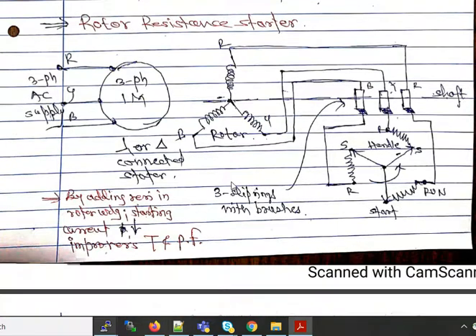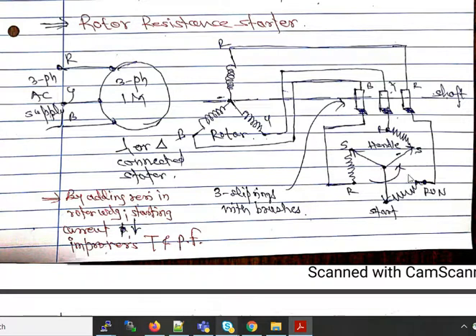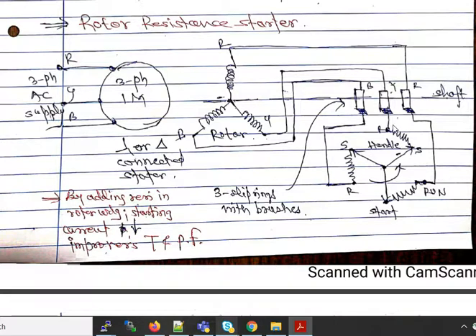The rotor resistance starter is used for the slip ring motor. The stator may be star or delta connected, but the rotor is always star connected — three winding terminals joined together, with the remaining three terminals connected to slip rings on the shaft with brushes resting on them. A Y-shaped handle starter is used: at the start position, maximum resistance is inserted in series with each rotor phase. As the handle rotates in an anti-clockwise direction, the resistance is gradually cut off until it is completely removed when the motor reaches running speed.